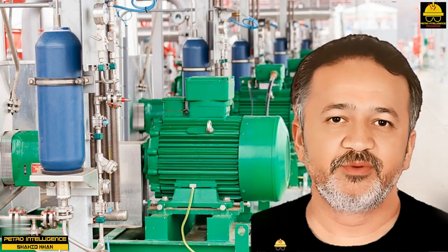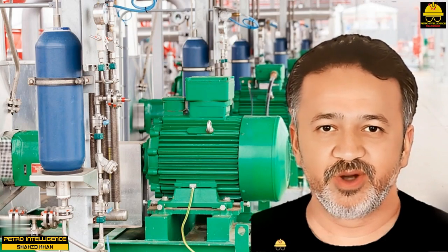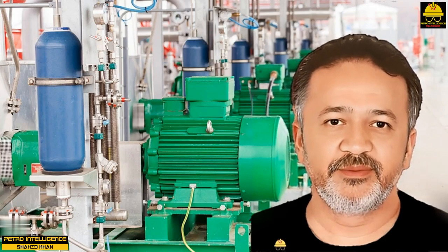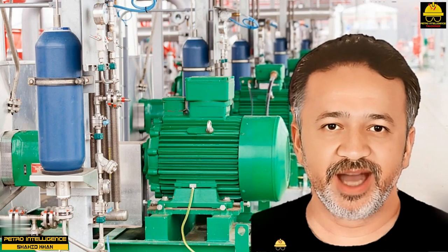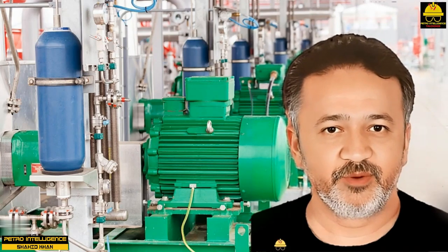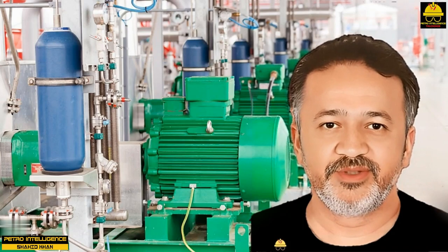Multistage pumps must never be operated with the discharge valve closed. Usually, a minimum flow system is designed into the piping so that there is always sufficient flow through the stages to protect them from damage.